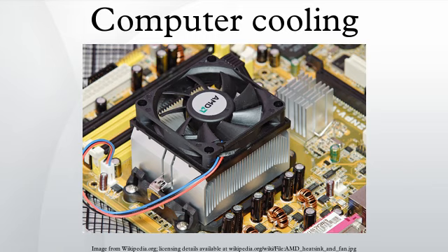Generators of unwanted heat. Integrated circuits are the main generators of heat in modern computers. Heat generation can be reduced by efficient design and selection of operating parameters such as voltage and frequency, but ultimately, acceptable performance can often only be achieved by managing significant heat generation. In operation, the temperature of a computer's components will rise until the heat transferred to the surroundings is equal to the heat produced by the component, that is, when thermal equilibrium is reached. For reliable operation, the temperature must never exceed a specified maximum permissible value unique to each component. For semiconductors, instantaneous junction temperature, rather than component case, heat sink, or ambient temperature is critical.